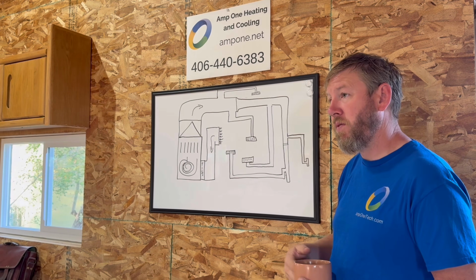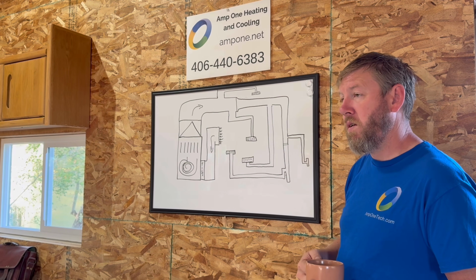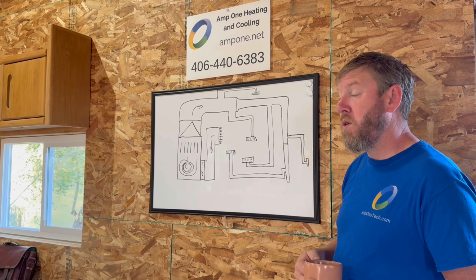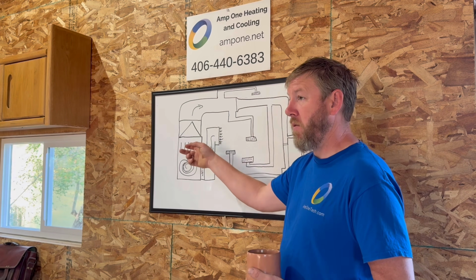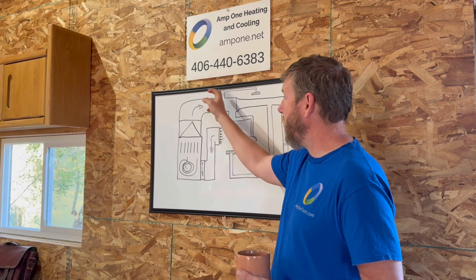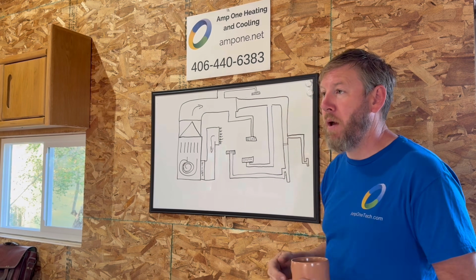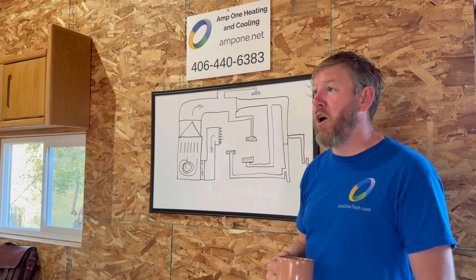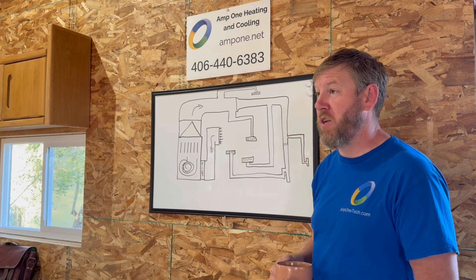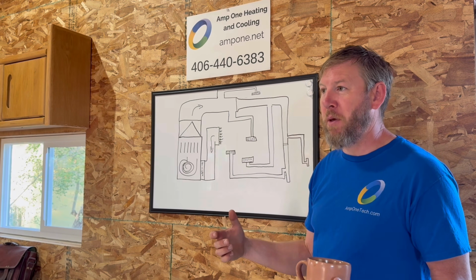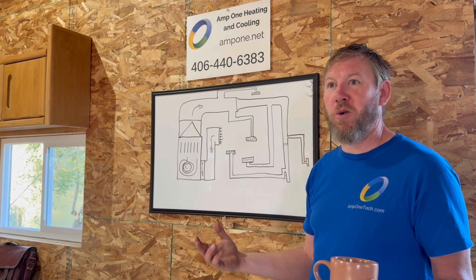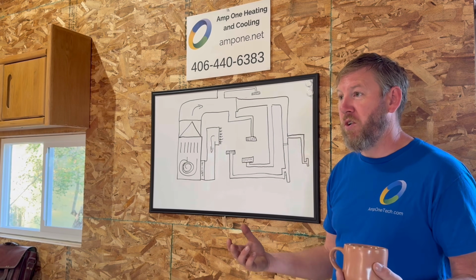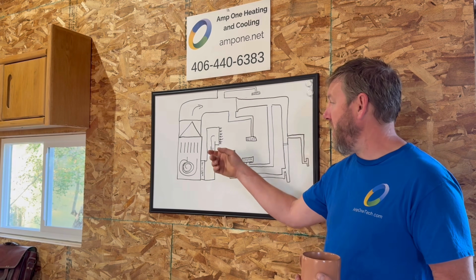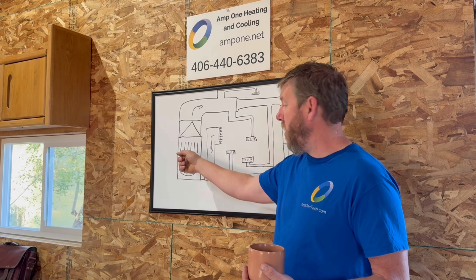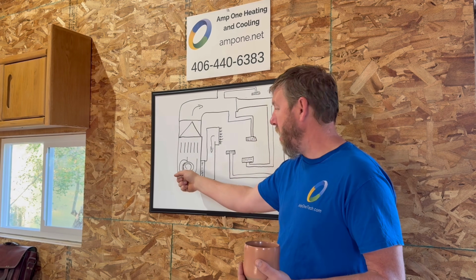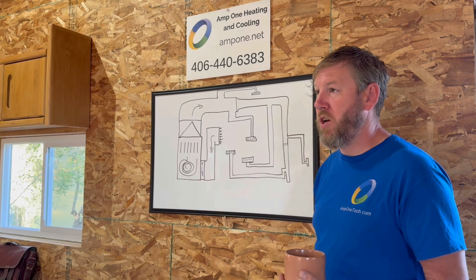So is there a formula or something that you use? Like, how do you know when to use reducers? Absolutely, yeah. It's actually that amount of airflow. Each one of these ducts can carry a certain amount of airflow. That's why Jesh and I were underneath the house for so long. We needed to get around some plumbing and make sure our airflow is going to stay up. We were checking math equations to see, each ton that a furnace pumps out, the furnace airflow is done off a tonnage.